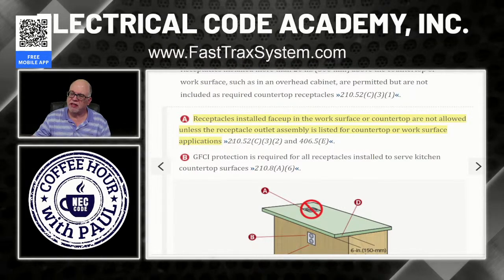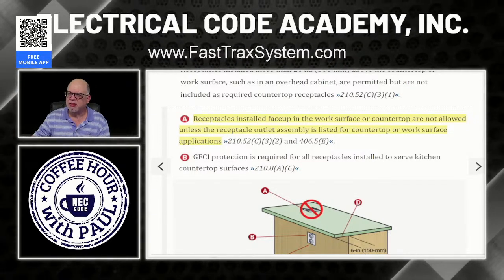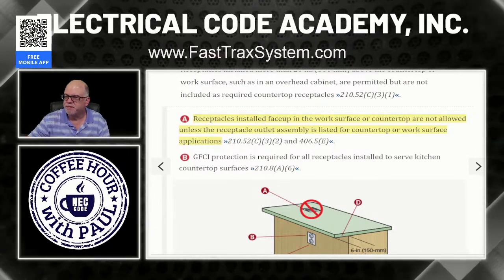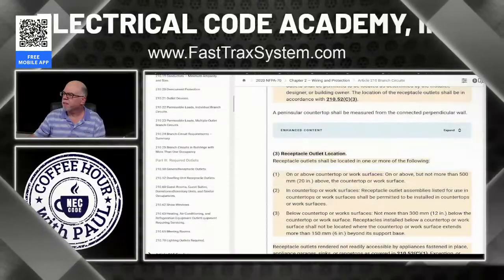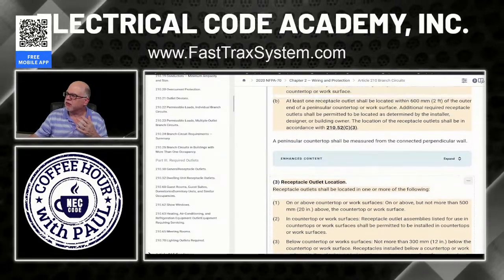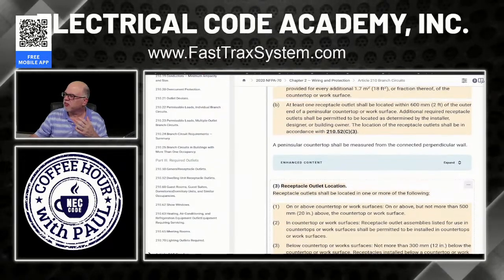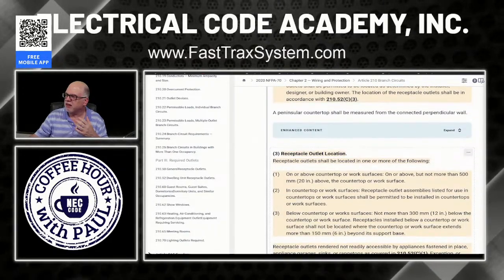And where does it give you that? It tells you this in 210.52(C)(3), as well as in 406.5(E). It gives you that direction. So let's go look at it real quick, 210.52(C)(3). Because I'm like you, I love going into the code and learning. So let's go into the code, 210.52, and we're going to go to C3 right here.